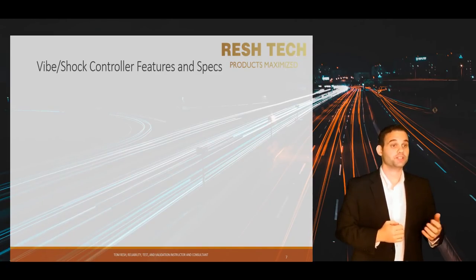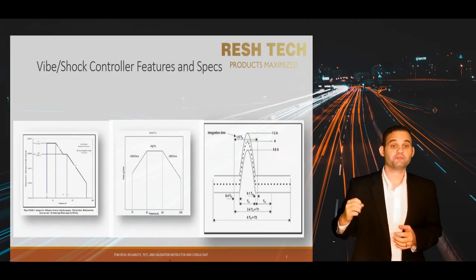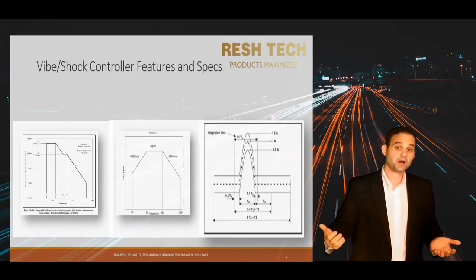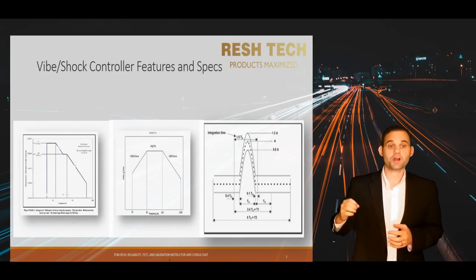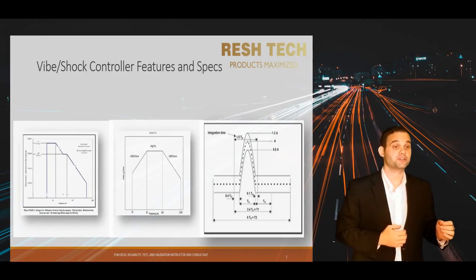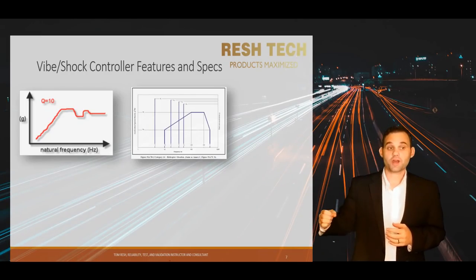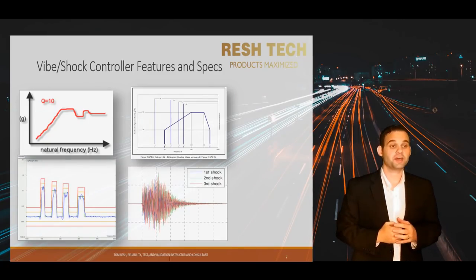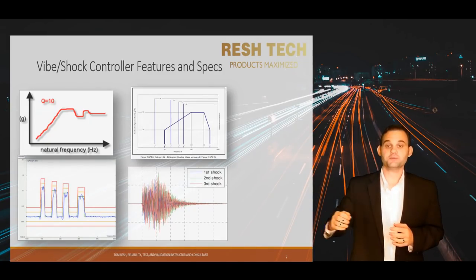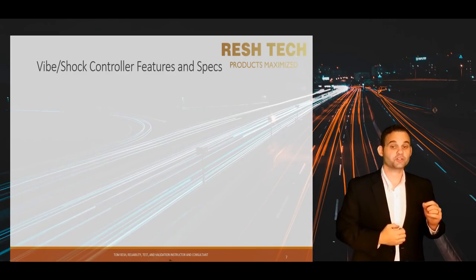For the software side, you also need to consider what types of tests you want to perform. Many vibe controller manufacturers provide sine, random, and classical shock as part of their standard package. However, most vibe controllers require additional payment for features such as shock response spectrum, sine on random, random on random, and field replication. You need to know what tests you will need to perform when purchasing a controller.